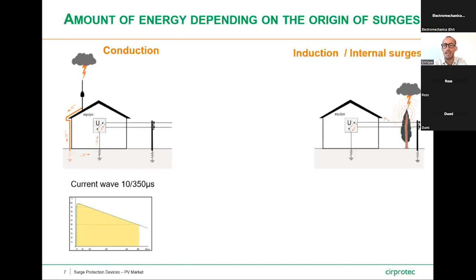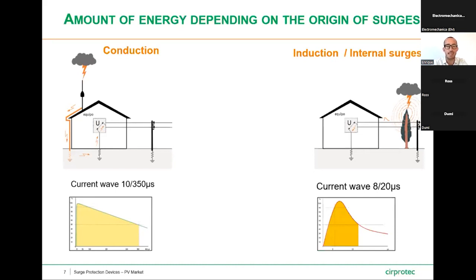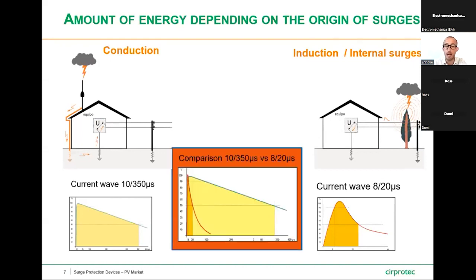Then, in the scenario of induction or internal surges, the standards set up a current waveform named 8/20 microseconds, which means the same: in 8 microseconds we get 90% of the total amount of energy, and in 20 microseconds it's reduced by 50%. If we overlap the two waveforms, we see that the most dangerous scenario to take care about is the one coming from conduction.